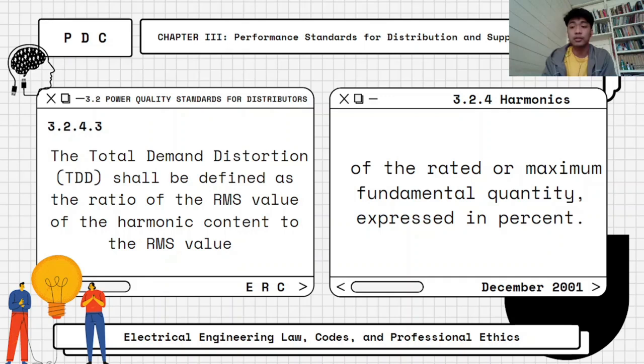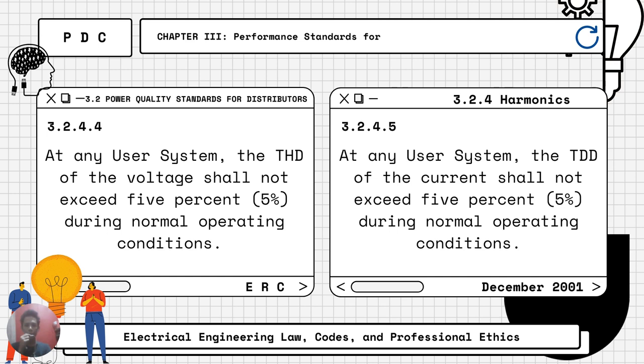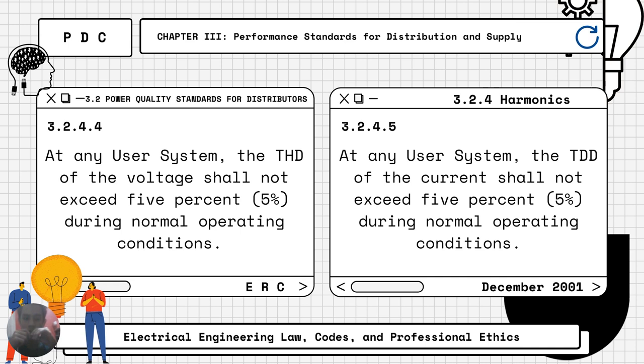Continuing the topic of harmonics under power quality standards for distributors: at any user system, the THD of the voltage shall not exceed 5% during normal operating conditions. Similarly, at any user system, the THD of the current shall not exceed 5% during normal operating conditions. Both the voltage and current THD limits are the same — they must not exceed 5%.